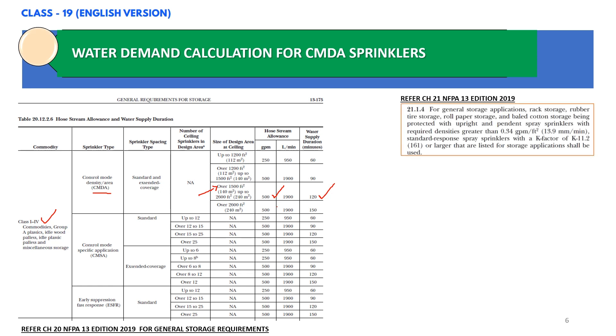As per NFPA 13 chapter 21, section 21.1.4, if our design density is greater than 0.34 gpm per square feet — and in our case it is 0.57 gpm per square feet — we have to use standard response spray sprinklers with a K-factor of 11.2 or larger that are listed for storage applications. Based on our scenario, we need to go ahead with K 11.2 or a higher K-factor.